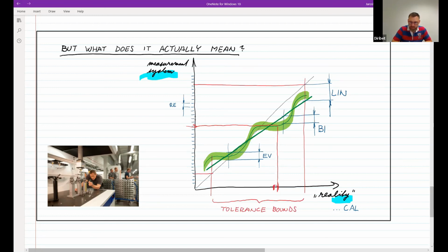And this is what matters. If you cover the biggest one, as I've shown you, because of this vector sum, you will be fine. You don't need to care about the little ones. If you are not sure, try to be a little bit conservative. If you say it is bigger than the reality and the measuring device will still pass, it still would be capable, that's completely all right. You don't need to worry about that.